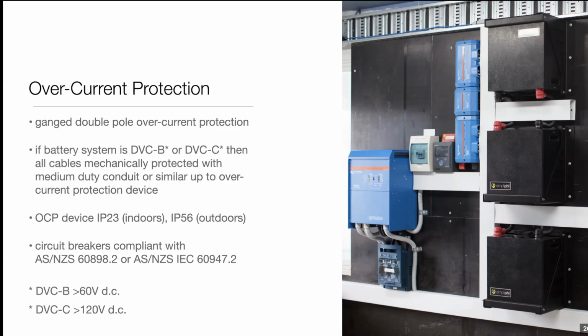A big change, and it's tripped up a few people already, is that we've introduced a new voltage classification system. Now, in AS/NZS 3000, we refer to ELV and LV. ELV, extra low voltage, is below 120 volts DC and 50 volts AC. But in this standard, we drop that reference to ELV altogether and refer to decisive voltage classifications. Now, these are an IEC classification matrix. It's actually a matrix because it depends on environment, nature of the supply, is it AC or DC, and the voltage level. And we have adopted the requirements for a dry location.